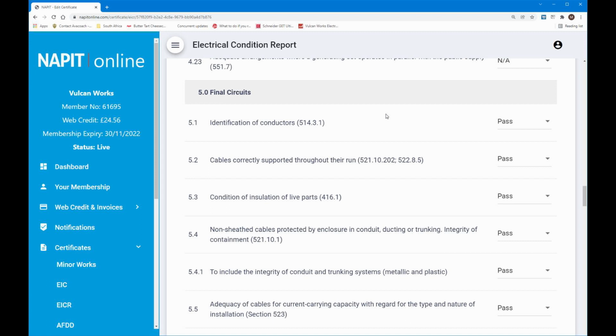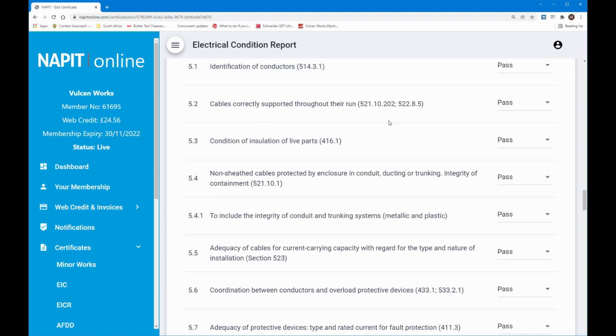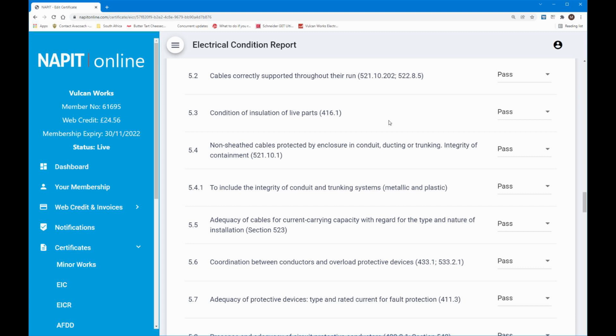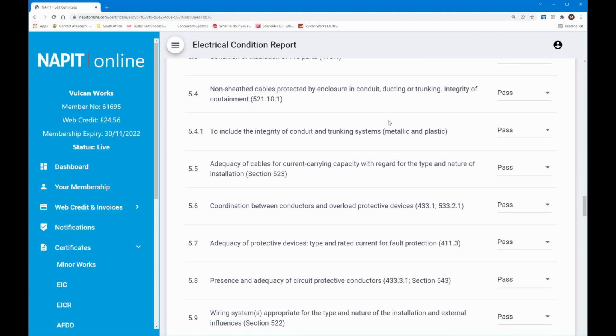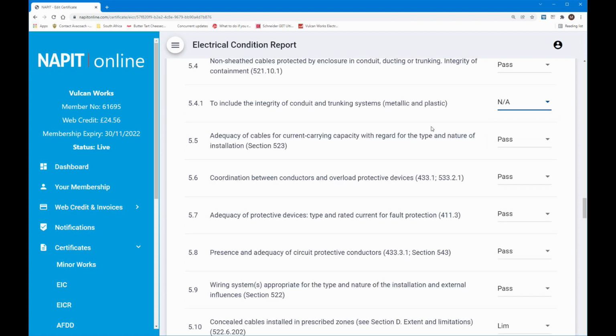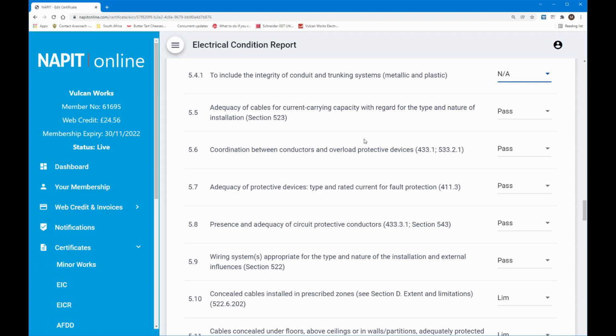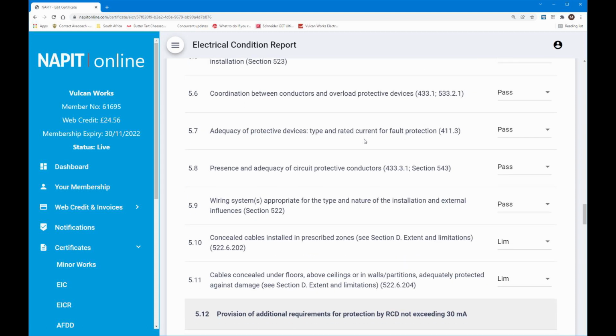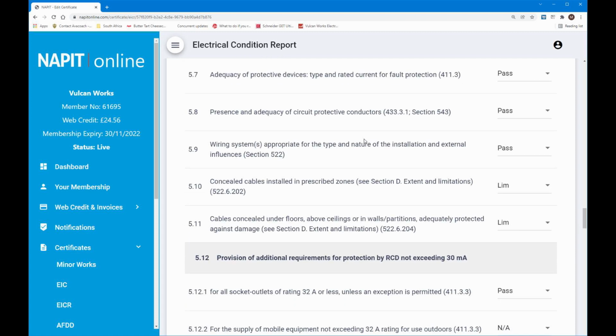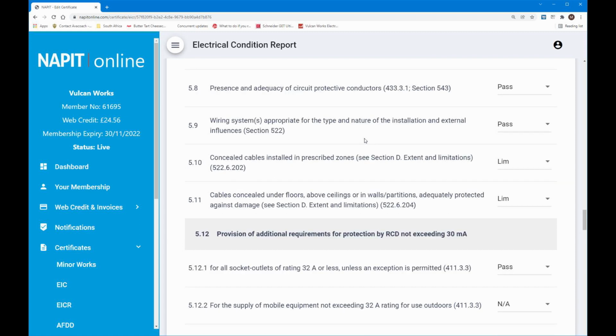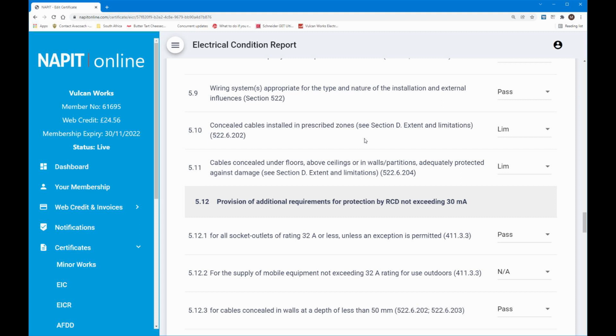Final circuits, all these pass, so identification, cables correctly supported, condition of insulation of live parts, non-sheathed cables done, integrity of conduit and trunking systems. Actually, I'm going to put that down as not applicable because there wasn't any. Adequacy of cables, yes. Coordination between conductors and overload protective devices, yep. Adequacy of protective devices, yes, that was fine. Adequacy of circuit protective conductors, yep, that was okay. The wiring systems are appropriate, they are. Concealed cables installed in prescribed zones. That's a limitation because I couldn't see that. There's no way unless I banged holes in the wall. I couldn't see it.